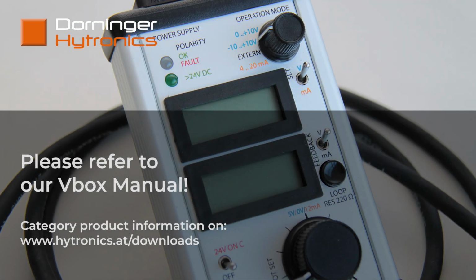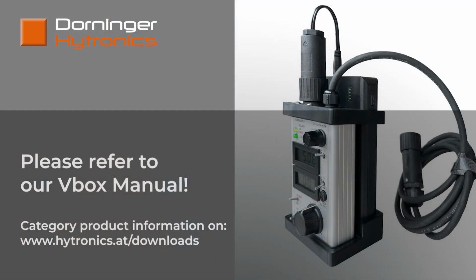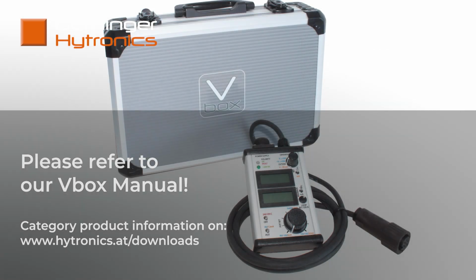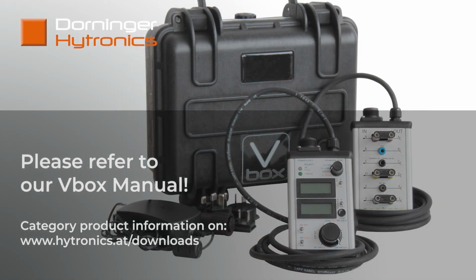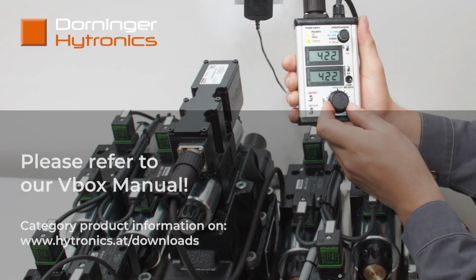Further information and safety instructions can be found in our Vbox operation manual. The work steps shown in this video are intended solely as guidance. Always observe the technical data sheets and safety instructions provided by the valve manufacturers. Once again we point out that particular caution is required when the hydraulic supply is active. All tests are carried out at the user's own responsibility.